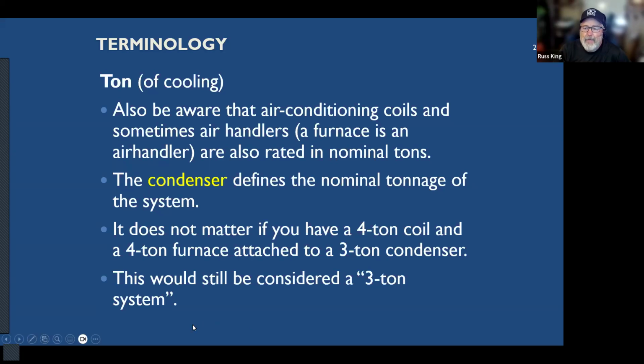And the coil and the air handler should always be bigger in tonnage than the condenser. You never want to do a 4 ton condenser with a 3 ton coil, because then you're pinching off the capacity. You're limiting its ability to be a 4 ton condenser by putting on a smaller coil. But you can always put on a bigger coil to try to squeeze a little bit more capacity out of that condenser. The condenser is like the engine, like the heart of the system.